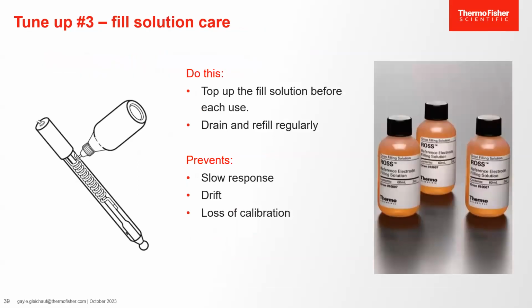Tune-up number 3, fill solution care. If you have a refillable electrode, top up the fill solution before each use. Regularly drain and refill the electrode to keep the electrode functioning as expected. In general, every 2 to 4 weeks is helpful. In your lab, it may be suitable to do this more or less frequently. Low, old, crystallized, or contaminated fill solution will cause slow response, drift, and loss of calibration.